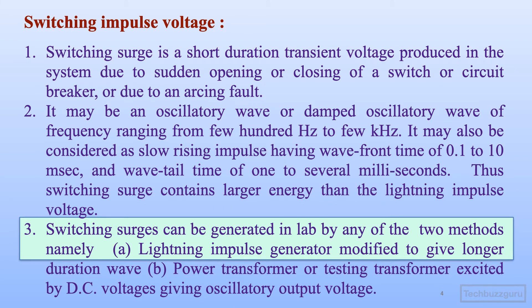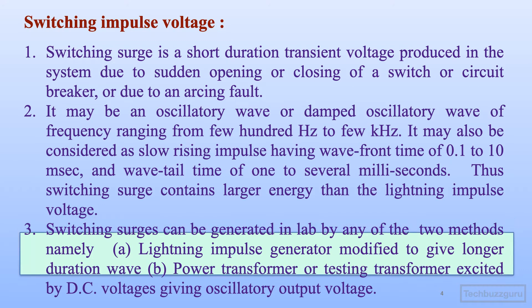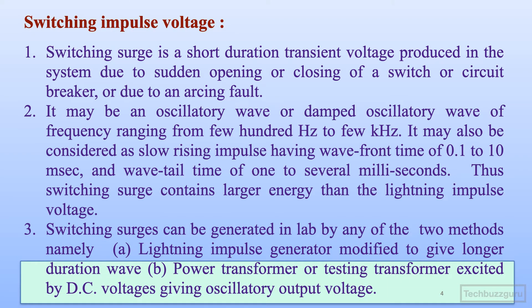Switching surges can be generated in the laboratory setup by any of two methods: first, by using lightning impulse generator modified to give a longer duration wave, and second, by using power transformer or testing transformer excited by DC voltages to produce oscillatory output.